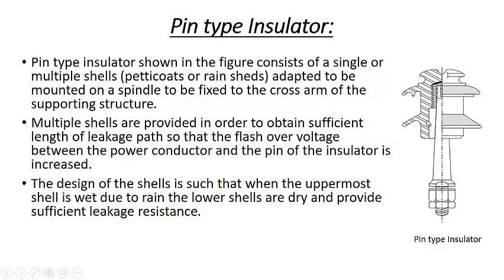It will not moisten the lower part of the lower petticoats. So that's why it is designed in this way. Multiple shells are provided in order to obtain a sufficient length of the leakage path, so that the distance for flashover between the power conductor and the pin of the insulator is increased. You can say multiple shells so that this distance, which is known as creepage distance, is increased, so that the flashover voltage is also increased.